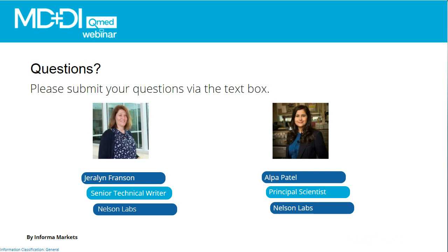Is FDA going to ask for alert and action levels for cleaning validations once ISO 15883-5 is finalized? I went through that on my slides, and FDA does not recognize action and alert levels, so I don't think we would have to worry about that for FDA submissions in the US. However, in Europe, it's still in the draft phase and has not been published, but it is going to be published this year.